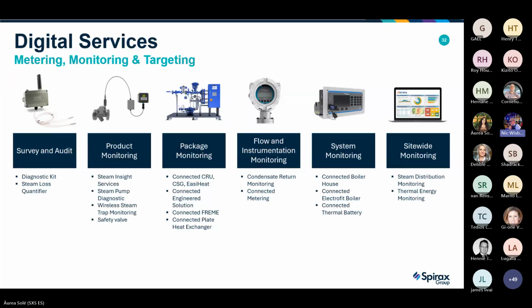Package monitoring, so all those sensors can be put on our packages. The item that's shown there is a heat exchanger unit. So we can also monitor that system, and you can see when it's working properly, what percentage is working efficiently, and so on. Flow metering, we can put Strata on any meter. It doesn't have to be one of ours, but we can meter your fuel, your water usage, your steam usage, even your effluent out. So you can have a real-time look at your losses, your usage, and the efficiency of producing steam, so how efficient your boiler is, by metering your production lines and your steam lines.